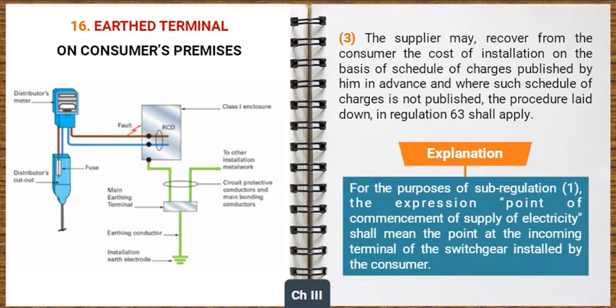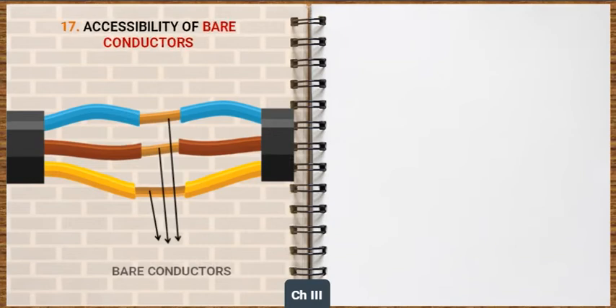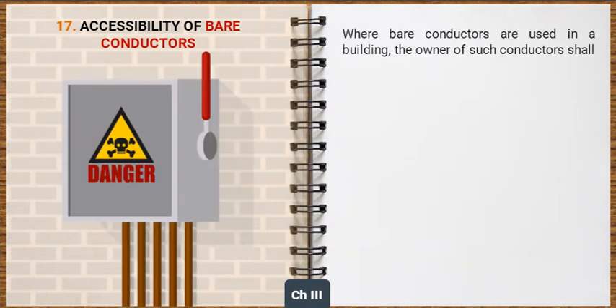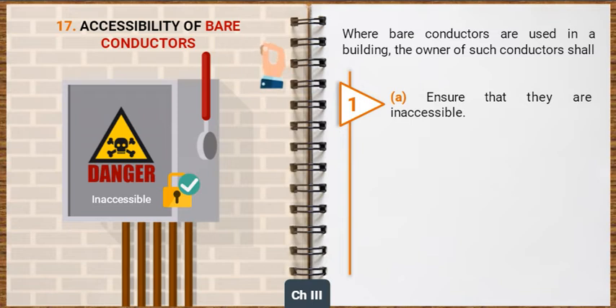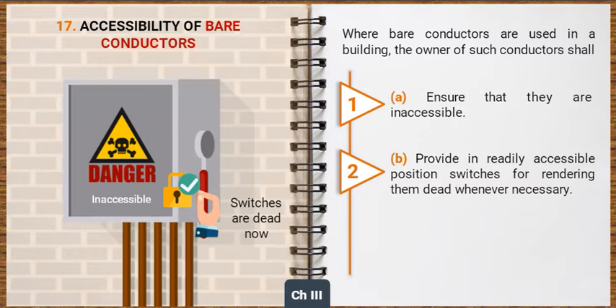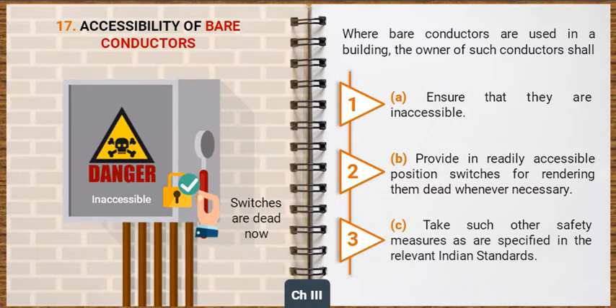For the purposes of sub-regulation 1, the expression 'Point of commencement of supply of electricity' shall mean the point at the incoming terminal of the switchgear installed by the consumer. Now let's learn about the general safety requirements for accessibility of bare conductors. Where bare conductors are used in a building, the owner shall ensure that they are inaccessible, provide readily accessible switches for rendering them dead whenever necessary, and take such other safety measures as are specified in the relevant Indian standards.